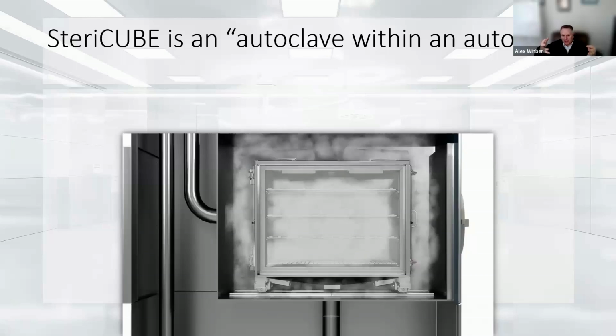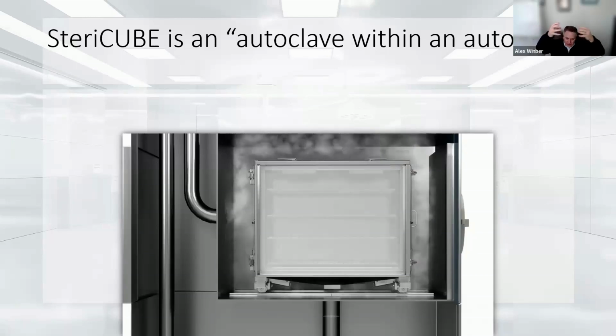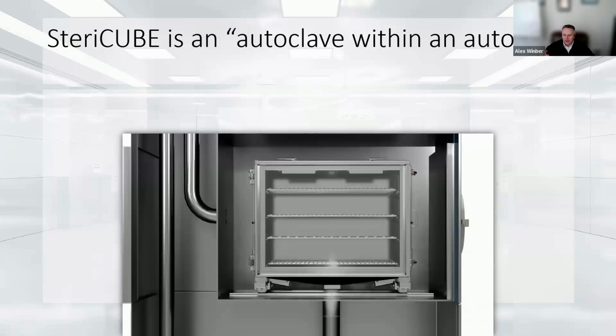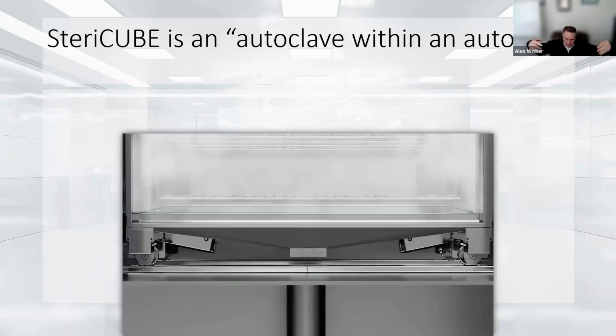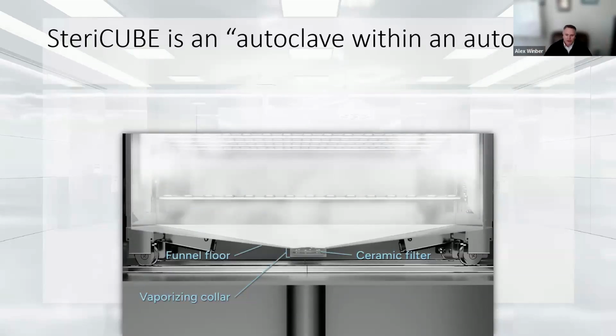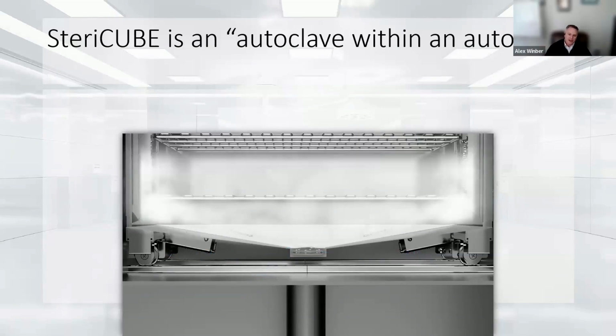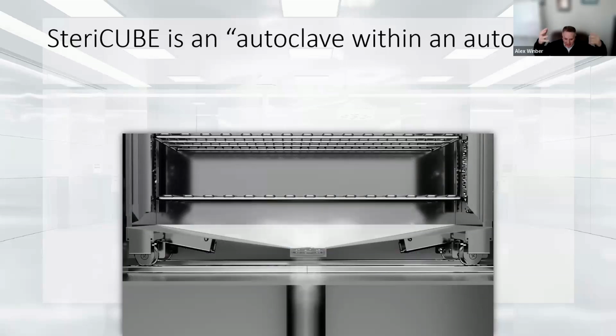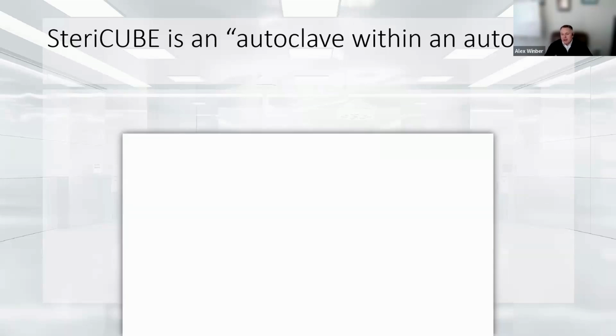Now, this is one cycle of the autoclave. A second cycle is the vacuum part, where it sucks all the steam out, and it gets sucked out through the bottom of the autoclave, and that's where we have our funnel floor. You can see the steam following the funnel floor along with any condensate that collects. We have a ceramic filter at the bottom to make sure nothing can come back in, and it all gets sucked out. And that's why with SteriCUBEs, we do not hear about the idea of a wet pack. That's not something that we have happen.